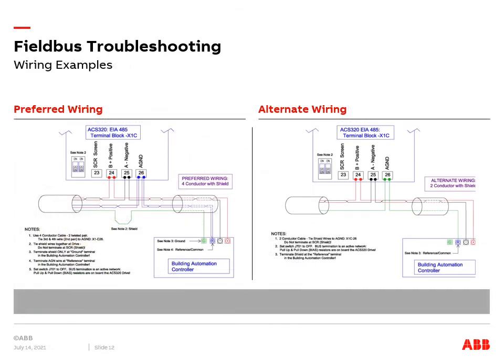There are two recommended methods of wiring field bus connections into the VFD's RS-485 terminals. One method utilizes a four conductor cable with a shield, while the other method uses a two conductor cable with a shield. The four conductor method is preferred, but the two conductor method is acceptable as an alternate wiring method.